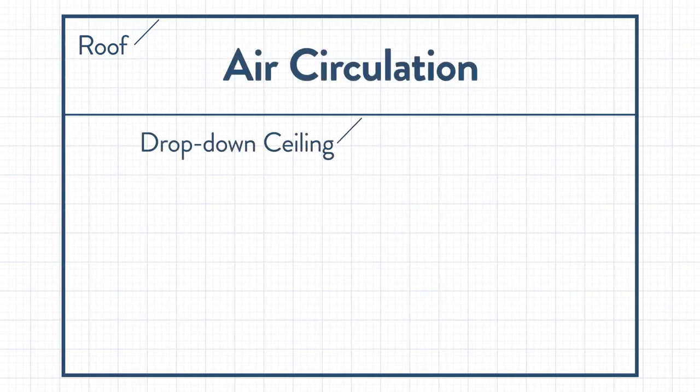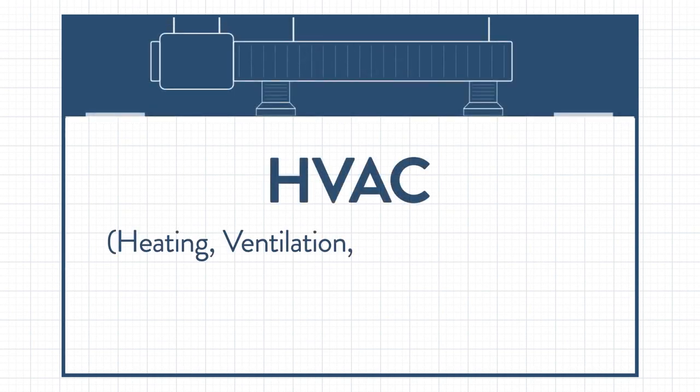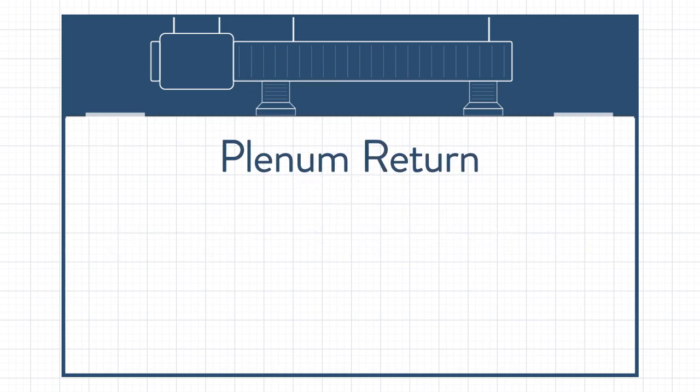A plenum is a separate space in a building, typically between the building's roof and a drop-down ceiling, that is primarily set aside for air circulation. This plenum space is purposefully designed to house HVAC equipment. In the HVAC world, these spaces are often referred to as plenum returns, but you might also hear it referred to as a plenum ceiling, a plenum space, or simply as the plenum.